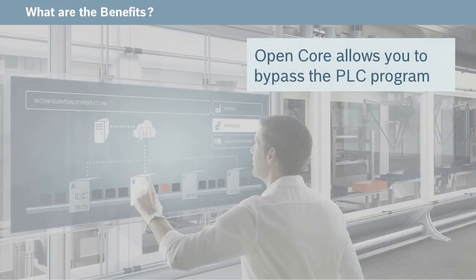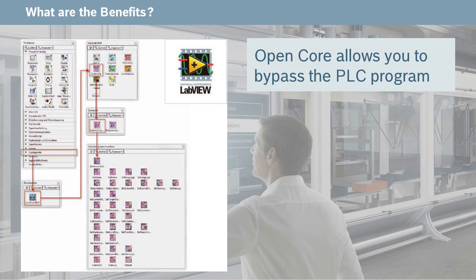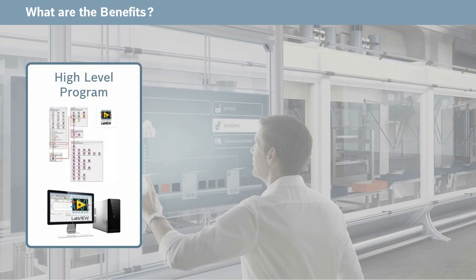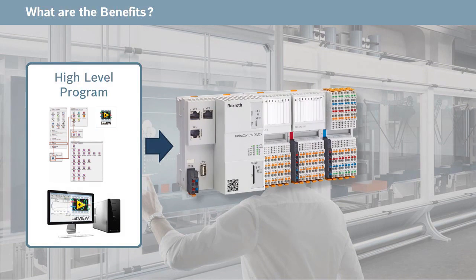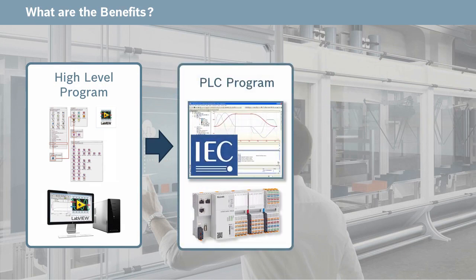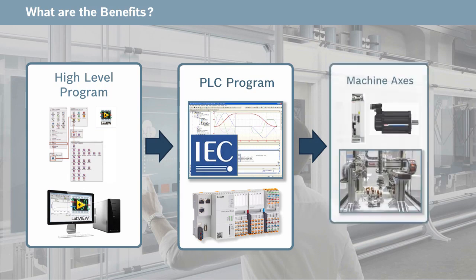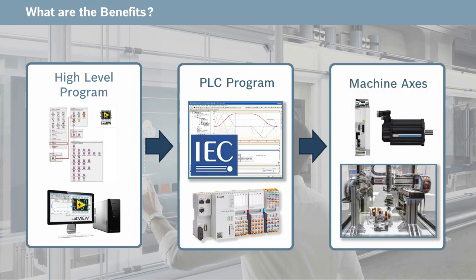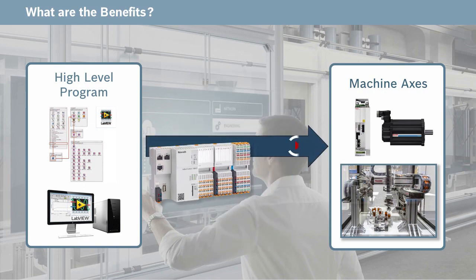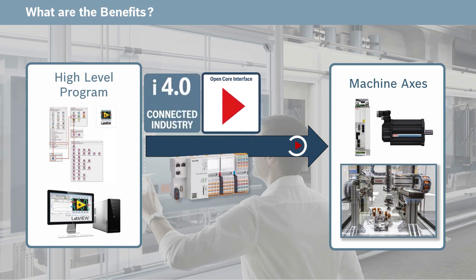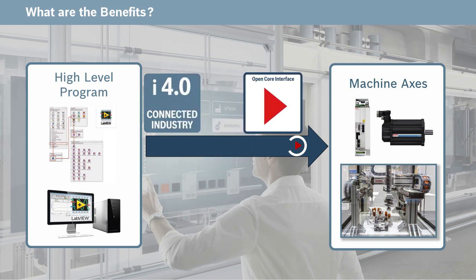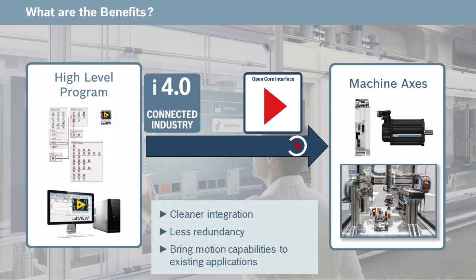Some of the customer benefits of the OpenCore interface: one of the most obvious is it allows them to get around the PLC program. If we think about a LabVIEW integrator who needs to get motion into a system, he would normally write an interface to our PLC, requiring a communication channel like OPC UA, EtherNet/IP, or some kind of field bus to get data from the LabVIEW system to the IndraLogic program to actually move motors and actuators. The OpenCore interface allows the LabVIEW user to access those core firmware commands and data directly, without needing the PLC program in the middle — giving him a tool set to move axes and read and control I/O directly from LabVIEW.